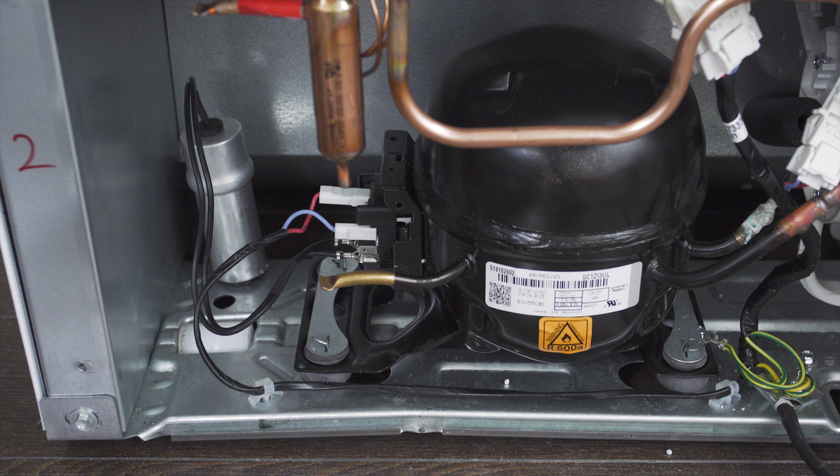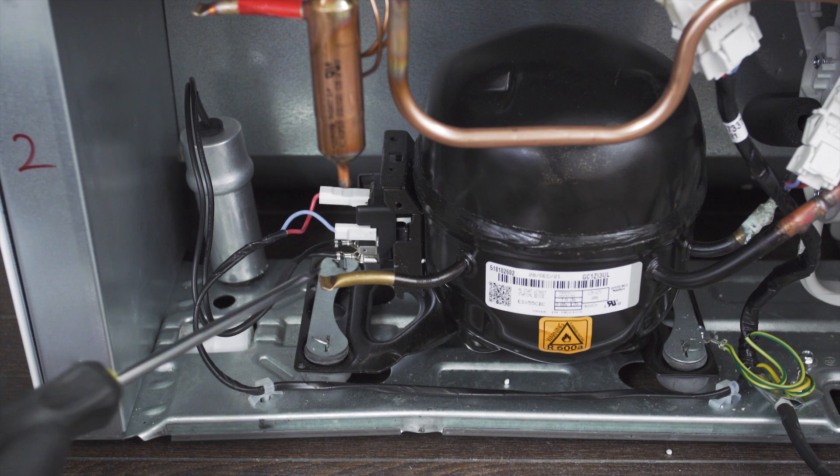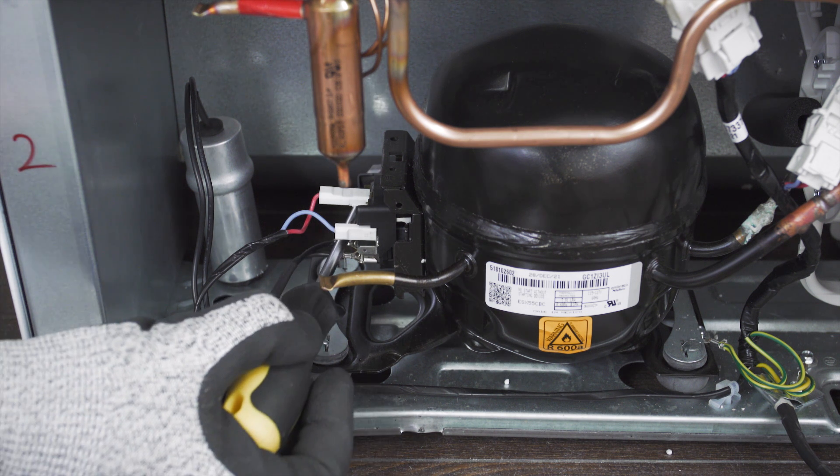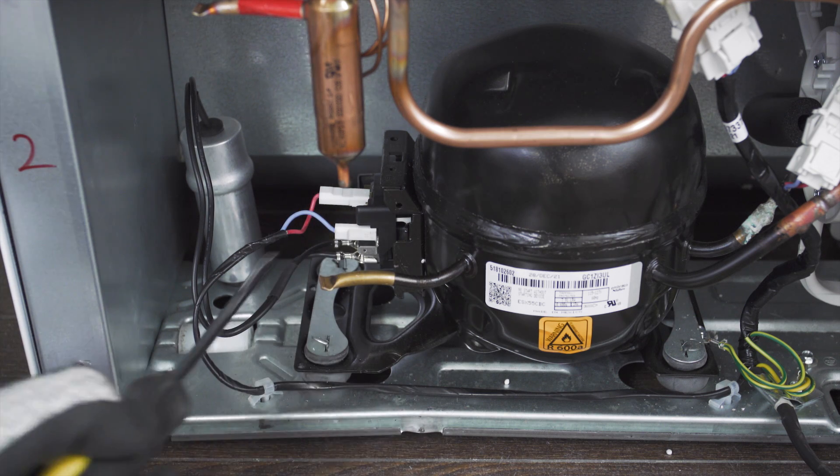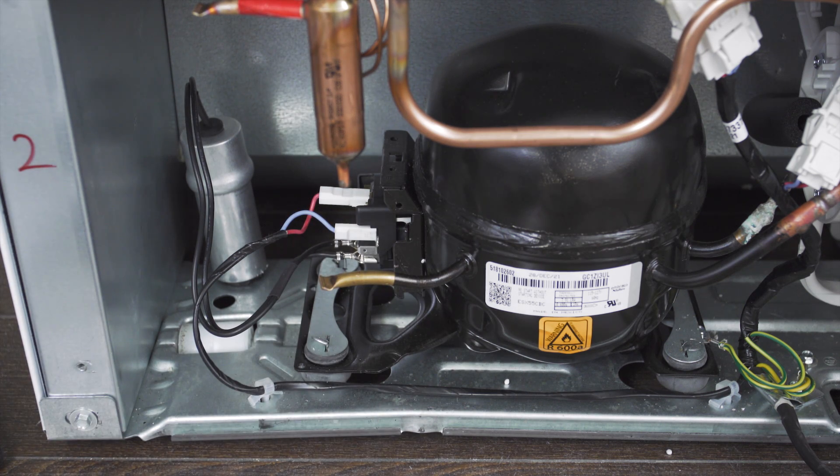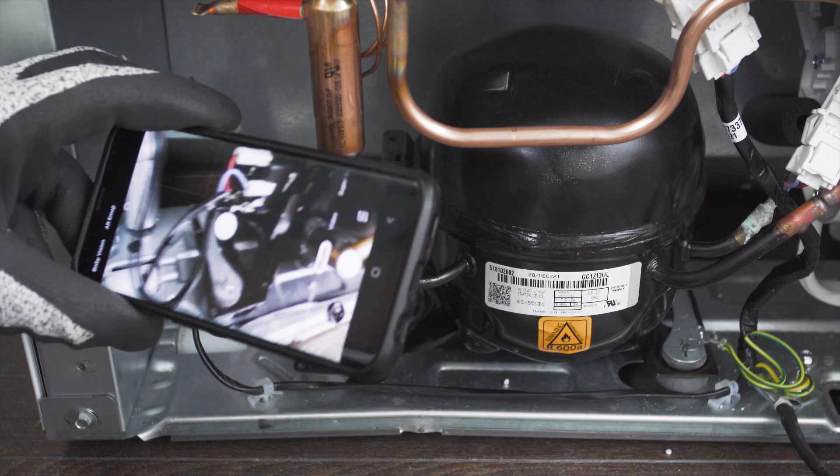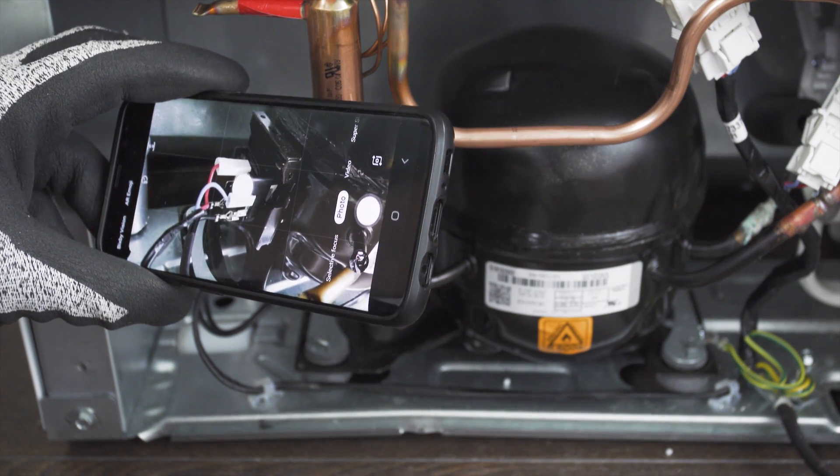Before anything else, use a high ohm resistor or a screwdriver with an insulated handle. Touch between the two terminals to release any stored energy inside the capacitor. Now take a picture of the wires for reference.